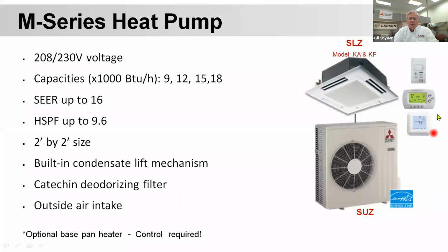And the default for these is to sense the temperature at this remote control, or at this, looks like a thermostat, at the controller. This one, you have to go into the menu and tell it you want it to measure the temperature there. And by the way, on all of the wall mount units that start with M, that come with a remote control, none of those remote controls sense temperature at all. They're just a remote control. They're designed to turn the equipment on, off, and so on, just like a TV. You turn the TV on, you set the volume, you set the channel, you put the remote down, and it stays there.